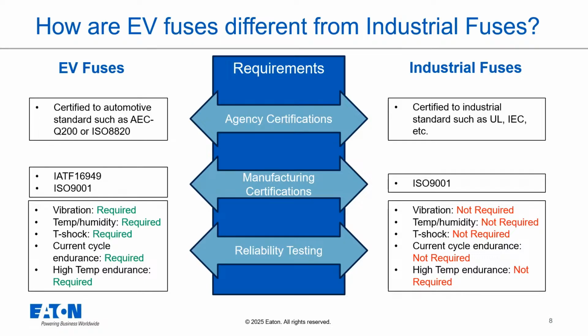The reliability testing is also much more stringent for EV fuses. Think vibration, temperature, humidity cycling, thermal shock, current cycle endurance, and high temperature endurance, all of which are required for EV fuses, but not required for industrial ones. In terms of application, EV fuses handle much higher voltages, up to 1,000 volts compared to around 500 volts for industrial. They also cover a much wider range of currents from sub-amp sensing fuses up to 600 amps or more for circuits and fast charging.